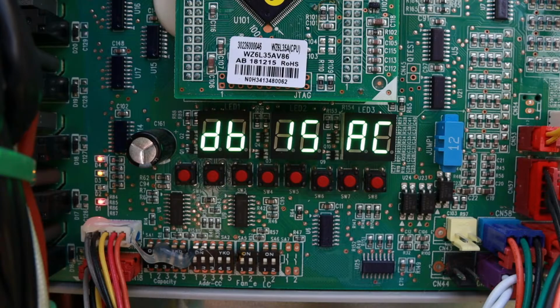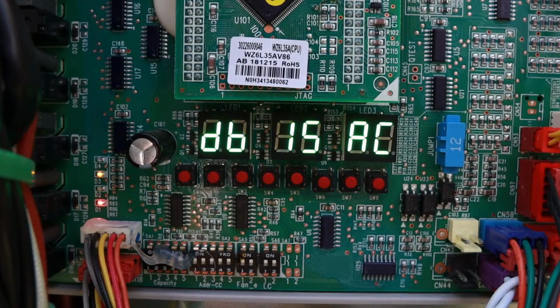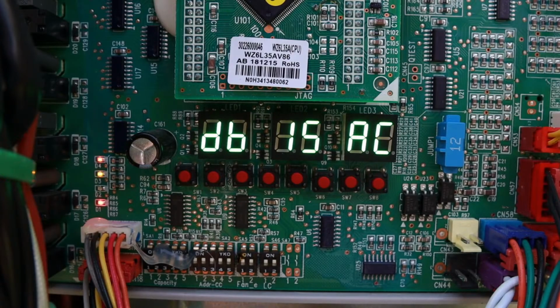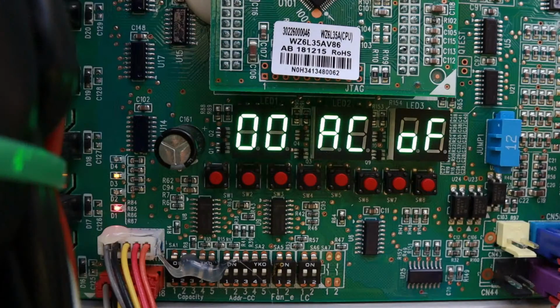On this step, the system will run at full speed and at all the possible combinations of configurations that we have in the system. So on a mini VRF, it will take about 40 minutes, and on a 3-phase cycle, it will take about an hour. So at this moment, all you have to do is wait, let the system run, and keep an eye on the LEDs and the display of the evaporators. When the commissioning cycle is finished, you will see on the LEDs 00 AC off. This means that the system has finished, and now the system is off. So it's time for us to go inside and turn on all the evaporators. Once you're done, just close the condensing unit, and then go back inside to check all the evaporators.